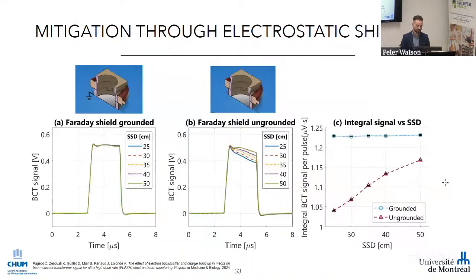So we did this experiment of comparing the signal when we have the electrostatic shield either grounded or not. The aluminum foil is there no matter what. It's just the fact of grounding it that activates our shield. When we have the shield in place, then we perfectly resolve this SSD dependence. We see the same pulse shape from 25 to 50 cm SSD. When the aluminum is there but not grounded, we still see this effect of pulse shape that changes as a function of the SSD. So it solved the SSD dependence.